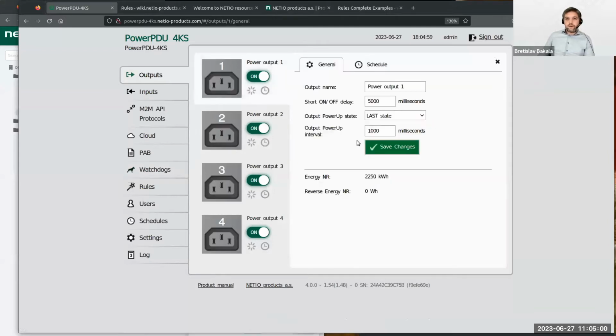Every output has a setup for the power up delay interval, set separately for every output, as an absolute time from the start of the device - you can specify it in milliseconds. By default, every output is differentiated by 1 second, so it automatically depends on the number of outputs - you can see the number changing here from 1 to 4 seconds.